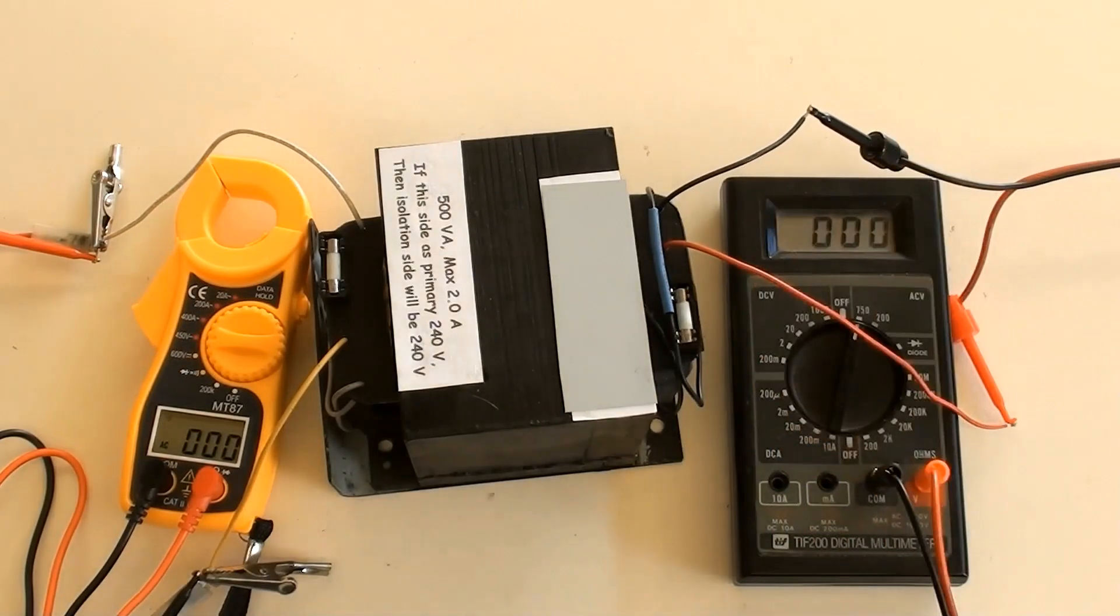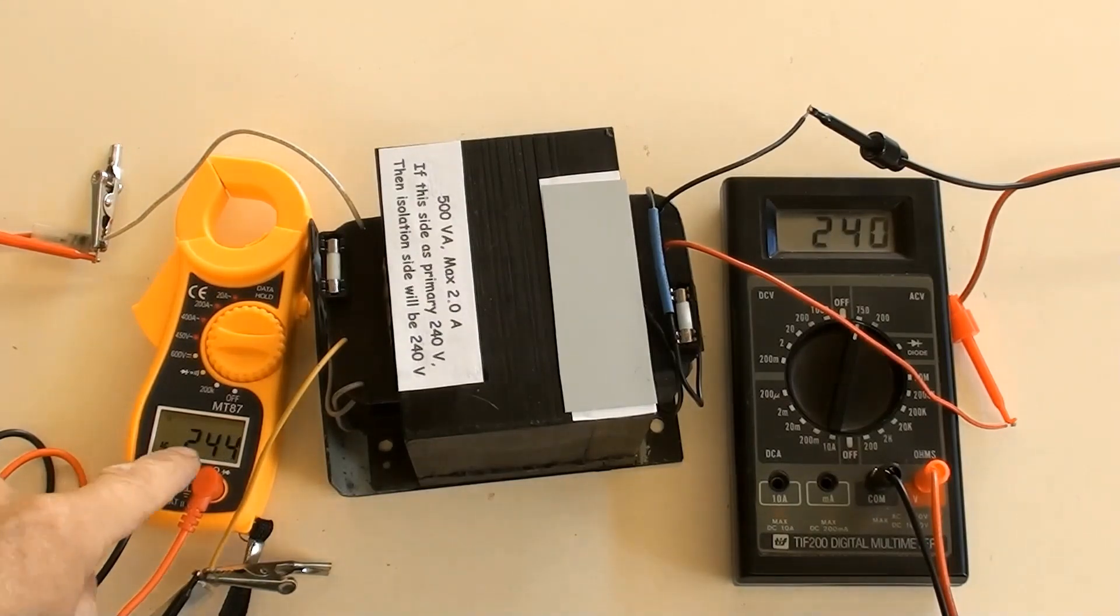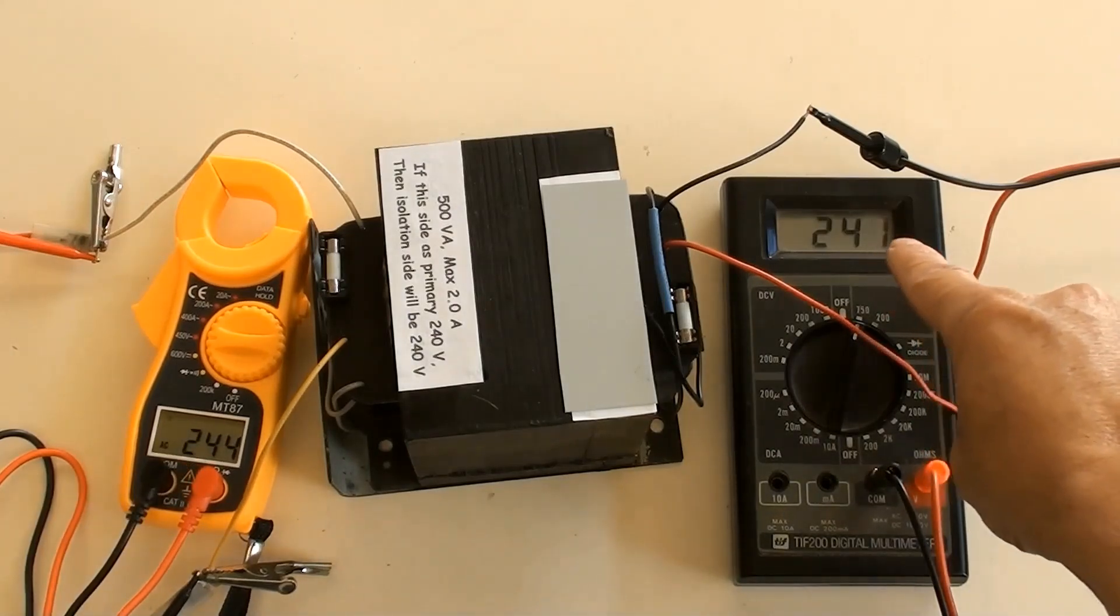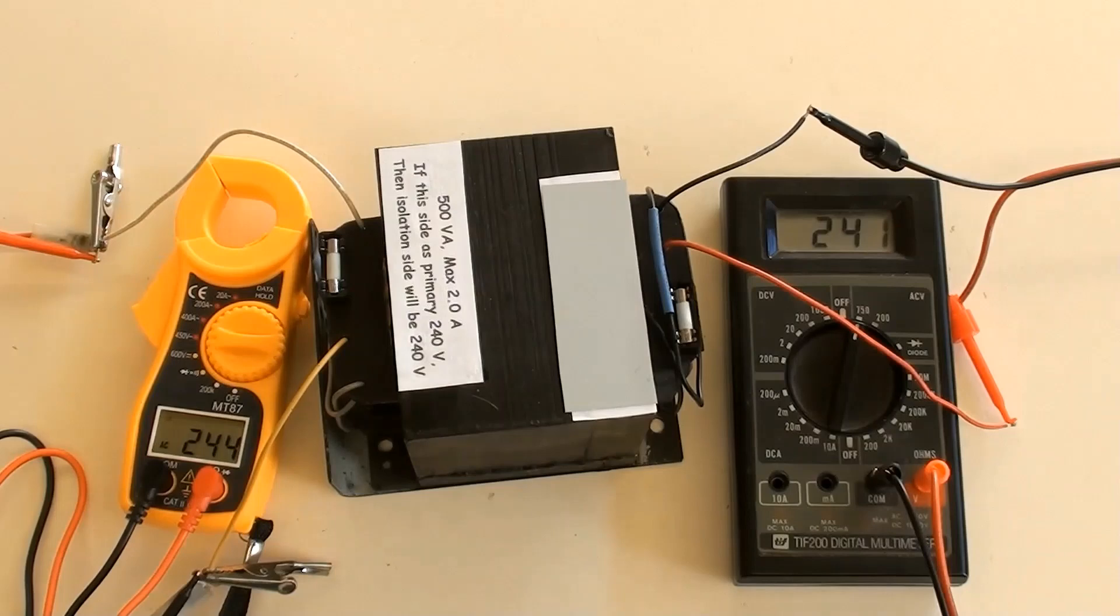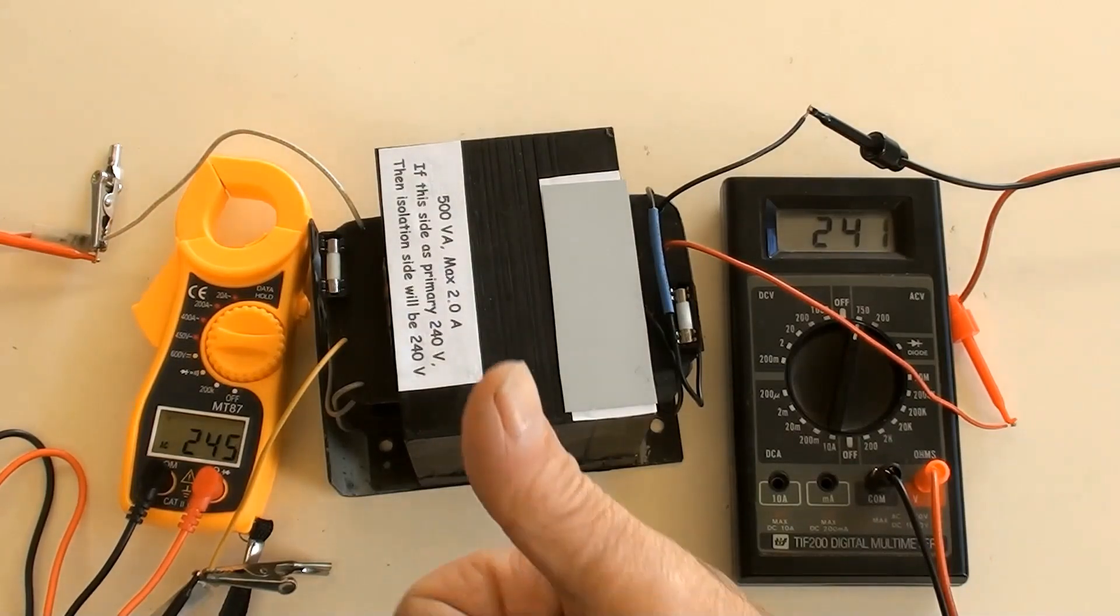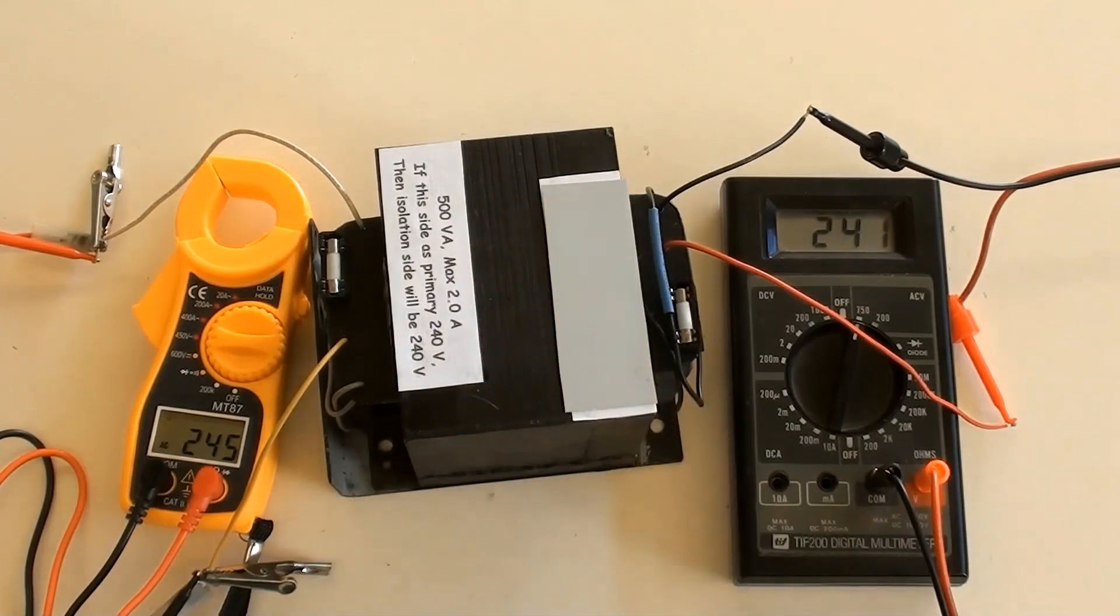These wires are the isolation side now. Switched power on. The voltage on the left primary is 244 volts, and the voltage on the right isolation is 241 volts. Although the two sides voltages are not exactly the same, only a few volts difference, it is quite okay with this tolerance.